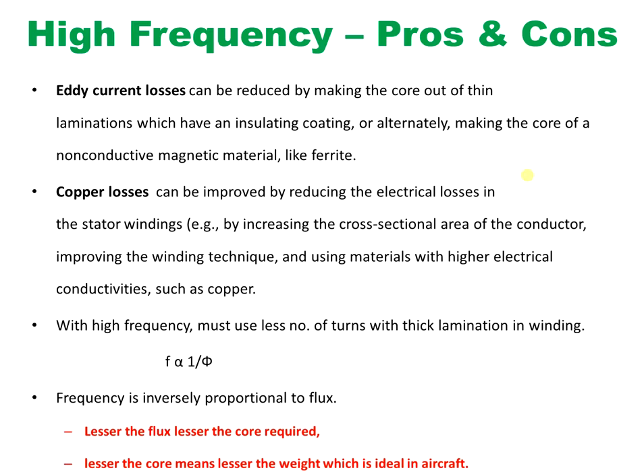Going from 60 Hz to 400 Hz, we do face some disadvantages. Eddy current loss may increase and copper loss will increase. To mitigate these: eddy current loss can be minimized by maintaining thin laminations in the core, and copper loss can be minimized by using high electrical conductivity materials like copper.